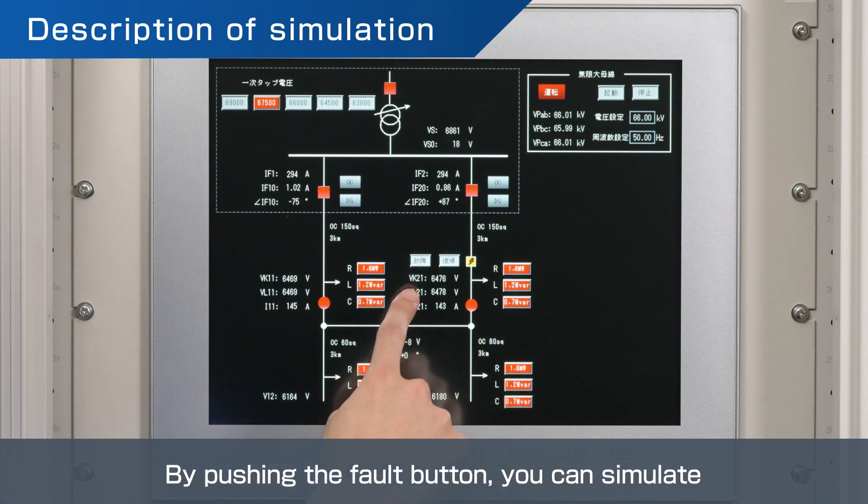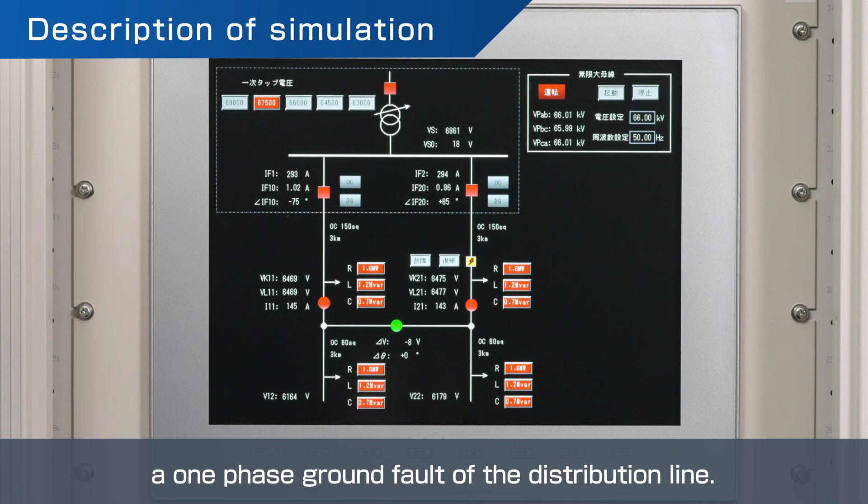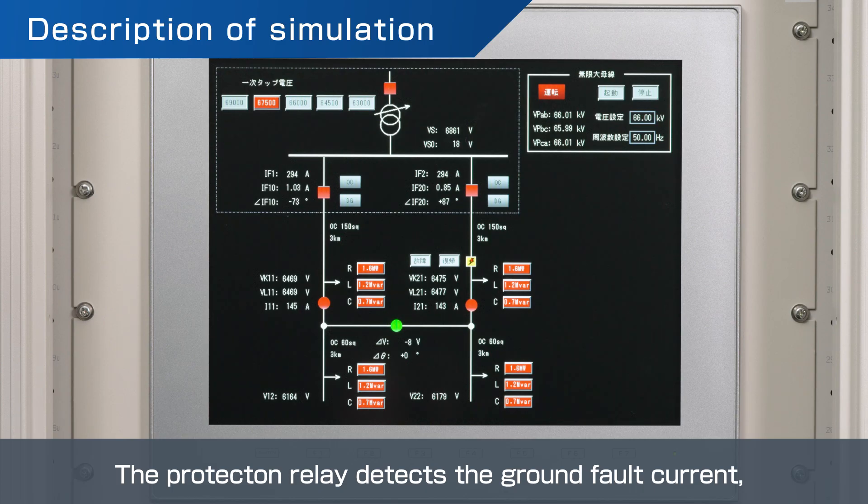By pushing the fault button, you can simulate a one-phase ground fault on the distribution line. The protection relay detects the ground fault current and the feeder circuit breaker opens.